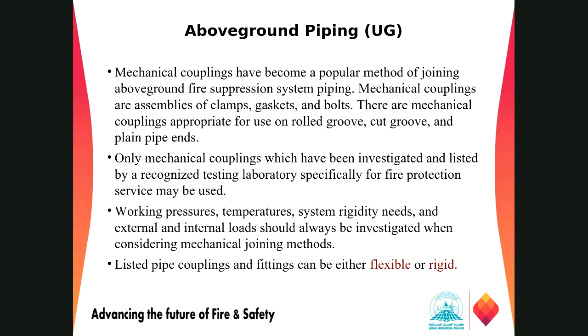If you remember, we discussed in fire protection design that if your pump suction and the fire water supply tank suction are on the same line, and you are connecting these two pipelines on different foundations, we must use an expanded coupling that allows regular movement of the piping without harming the pipe. Flexible couplings work in the same way, right? A flexible coupling is defined as one that permits axial displacement, rotation, and at least 1 degree of angular movement. It will allow 1 degree of deviation of the pipe from the center line, and it will protect the pipe from getting damaged due to settlement of the pipe from time to time.